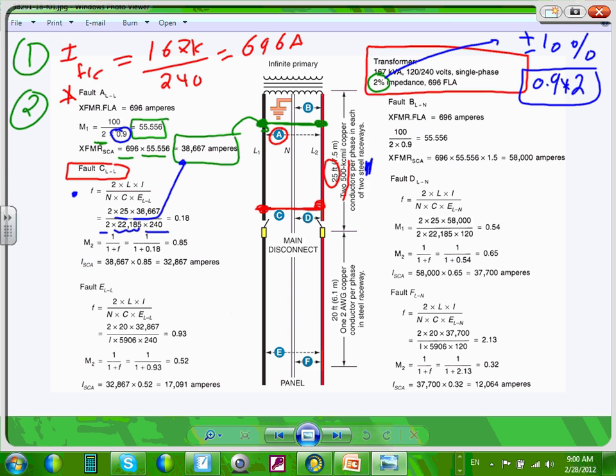What is the C for this table? 22185. Can you guys see where this 22185 came to be? Now what the heck is this? This is the impedance. This is equivalent to the impedance of the conductor. Now, thank God, on the software we don't have to mess around with tables like this. All of them are embedded in the system. That's the impedance, the R and the XL and the XC of your conductor, equivalent to the Z of your conductor. Can you guys see that they can give it to you for different conductors, for copper, and different voltages? Cool?